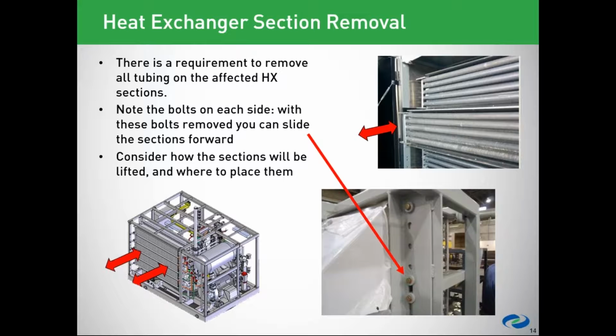So continuation of the heat exchanger section removal, there's a requirement to remove all tubing on the affected HX sections. Note the bolts on each side. I've already discussed this. And consider how the sections will be lifted. That's your only real concern here, is that we are able to pick them up and set them down. There are lifting points. If you can get some kind of overhead crane available, or again, with the development of this new tool that we're working on, basically we'll be able to slide these things out and possibly pick them up and set them down.